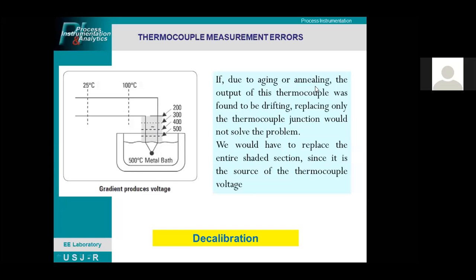So if, due to aging or annealing, the output of this thermocouple was found to be drifting, replacing only the thermocouple junction would not solve the problem. We have to replace the entire shaded section since it is the source of the thermocouple voltage for this junction. So it needs to be replaced just in case, since there are a lot of errors due to this aging or annealing.